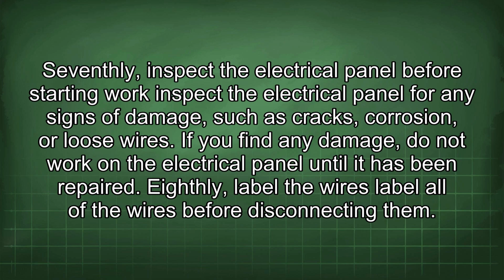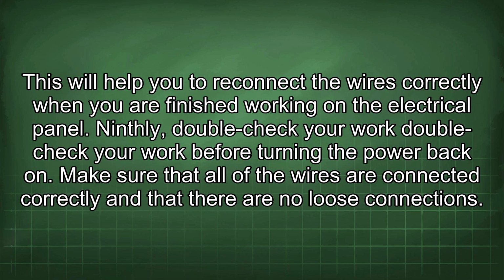Seventhly, inspect the electrical panel before starting work. Inspect the electrical panel for any signs of damage, such as cracks, corrosion, or loose wires. If you find any damage, do not work on the electrical panel until it has been repaired. Eighthly, label the wires. Label all of the wires before disconnecting them. This will help you to reconnect the wires correctly when you are finished working on the electrical panel.